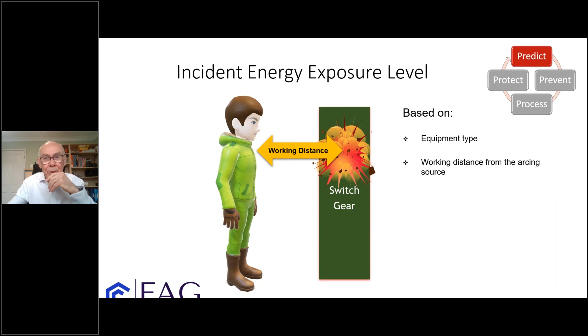So the first thing that I talked about, what incident energy calculations do, is give us the calculation for calories per square centimetre, the incident energy at the working distance given here, whether it's testing or switching or reading meters or whatever. And it's a working distance from the arcing source.